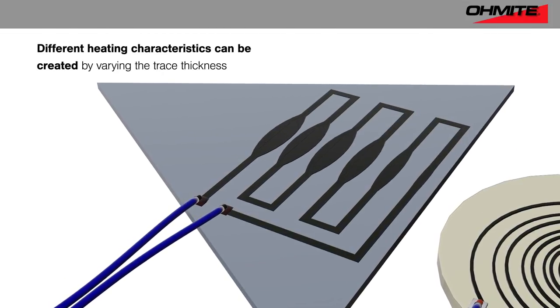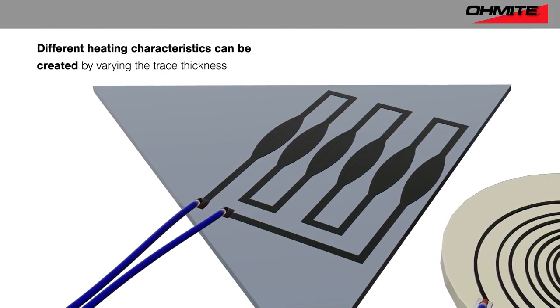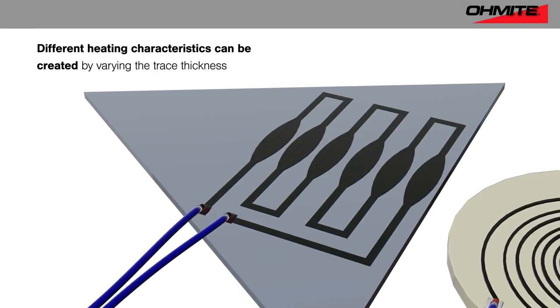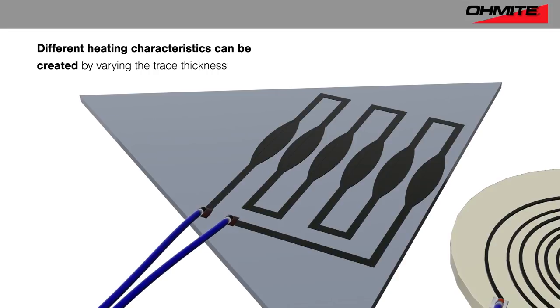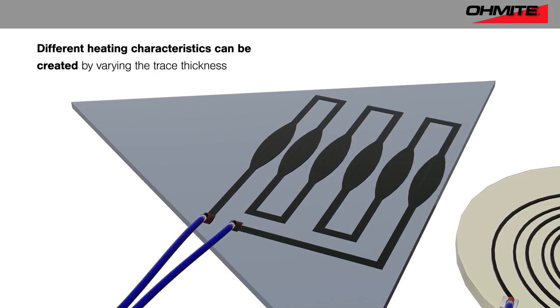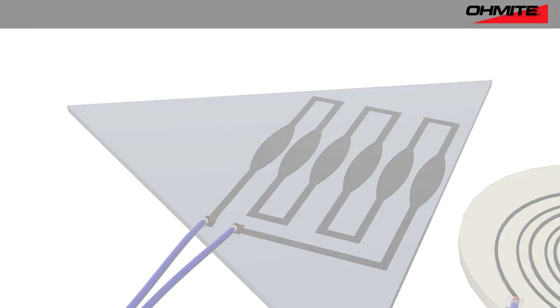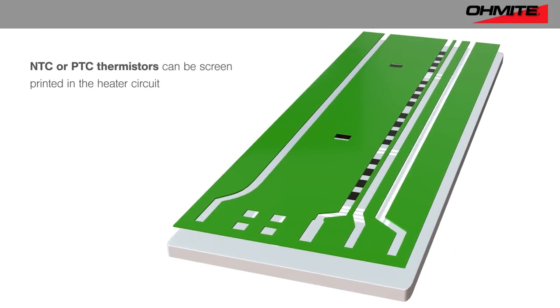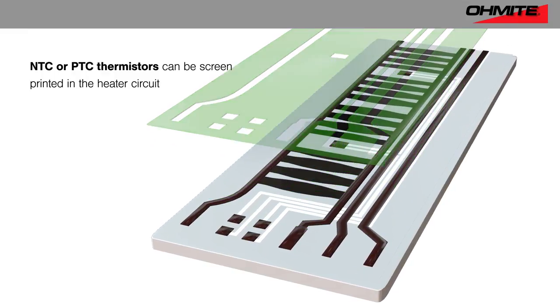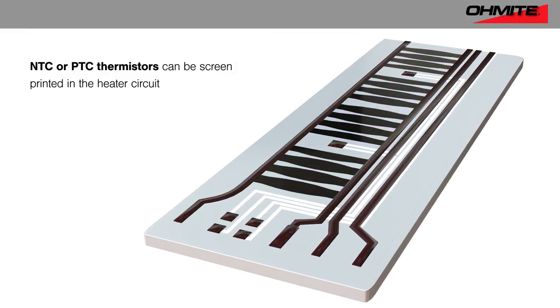Ohmite's process supports variable trace thickness to easily create areas with different heating characteristics. Ohmite R&D engineers are continuously testing different combinations to provide customers with baselines to work from, to meet the needs of different applications. Ohmite is also able to screen print NTC or PTC thermistors in the heater circuit, to shut down the heating element once a predetermined surface temperature has been reached.